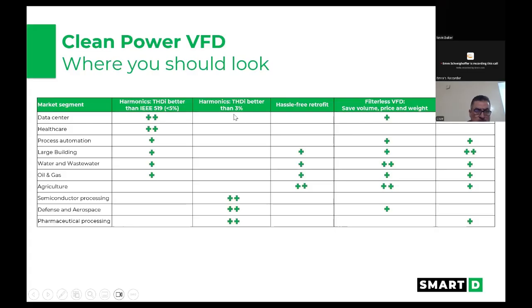So there are some areas that require even more stringent harmonic mitigation than you would be asked for from this standard of IEEE 519. Retrofit's great for us because you can keep your old motors, you can keep your old cables. The example that Thierry was talking about just now, I believe. Was it them? I believe, yeah, they were. I think it was the 1,400 foot cable length. Thierry, was that the? Yeah, I mentioned it before the meeting started. There's a 50 horsepower submersible pump 1,400 feet away from the VFD, connected with an old underground cable. Nice. Yeah. So no need to upgrade your cable or your motor when you put our drive on there as a retrofit.